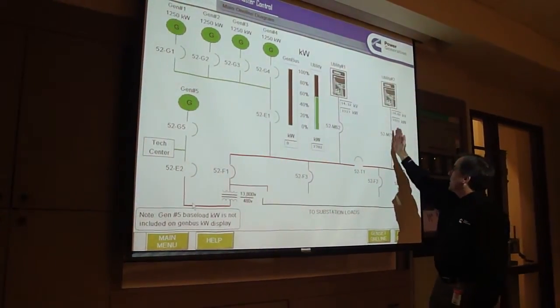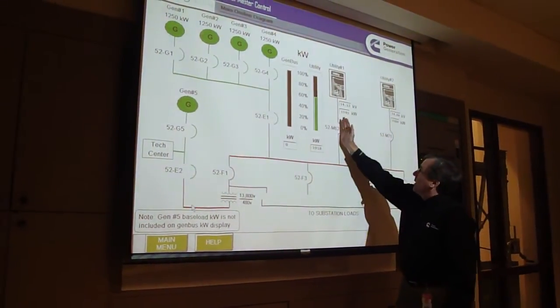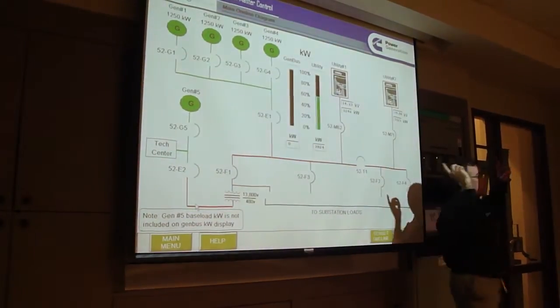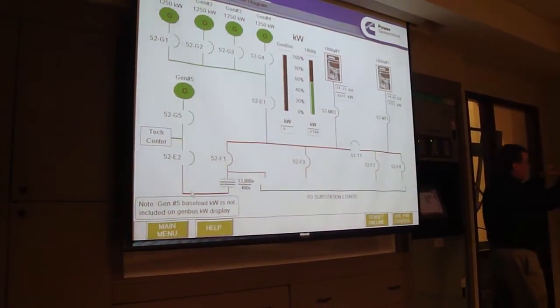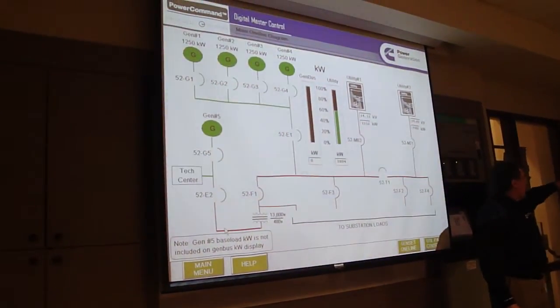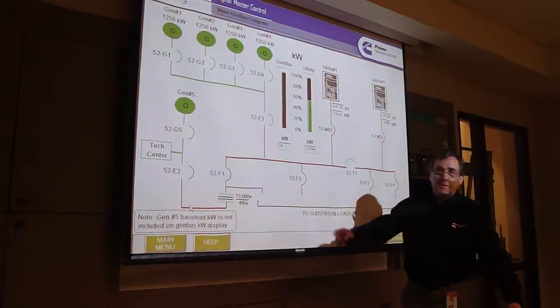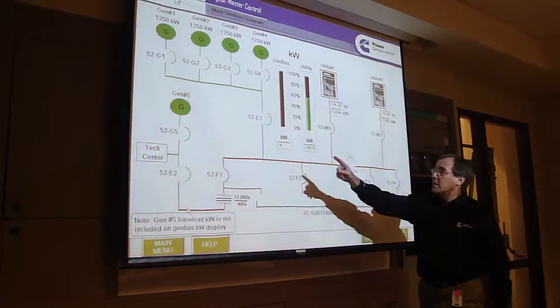So we'll close this, open that, all the power will be transferred to this utility. The start signal will be sent to the generators, all of them at the same time. Doors will go up. Then it becomes a race — the generators start to close onto this bus. You'll hear them bang, bang, bang, close.